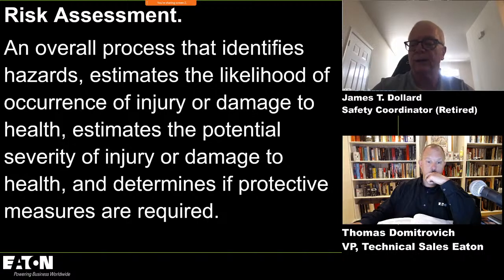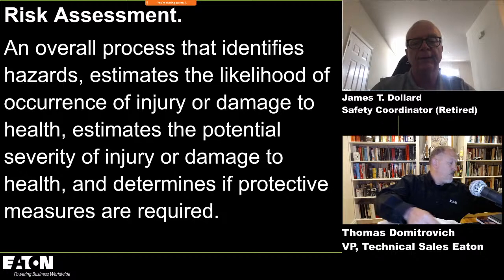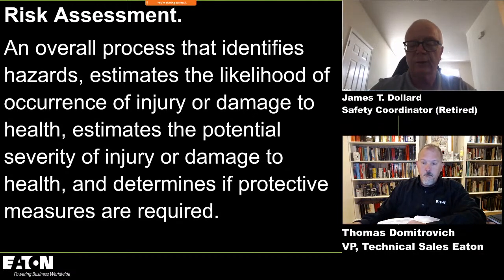So for example, we identify exposed, energized conductors or circuit parts. Then we estimate the likelihood of occurrence of injury or damage to health. So what we're looking at now is our task. And we say, okay, is it likely that we put ourselves into a shock situation and get current flow through the body? Then we estimate the potential severity of injury or damage to health. And a 120 volt circuit would be dynamically different than one leg of a 4160 volt or 5 kV system. And then we determine if protective measures are required. That's the last step.